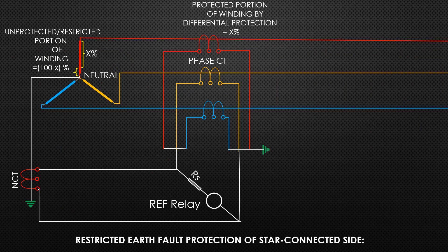By differential protection scheme, 90 to 95 percent of transformer winding is protected. The remaining 5 to 10 percent is left unprotected. When a fault occurs very near the neutral point of the transformer, the voltage available for driving earth fault current is small.